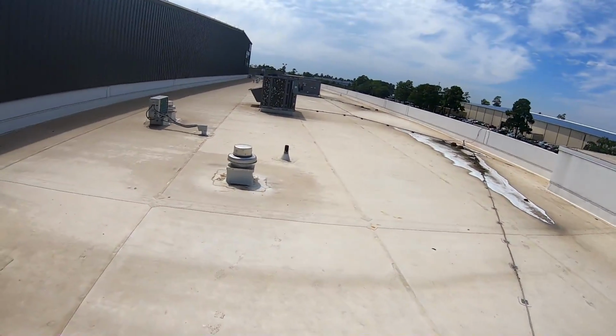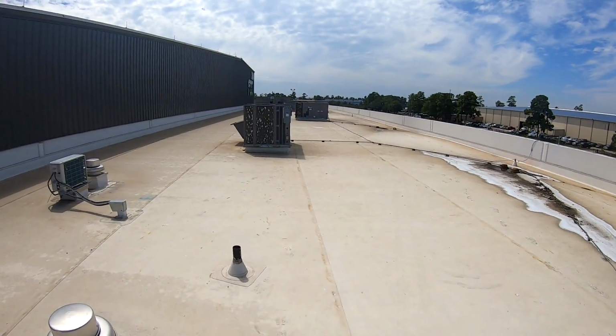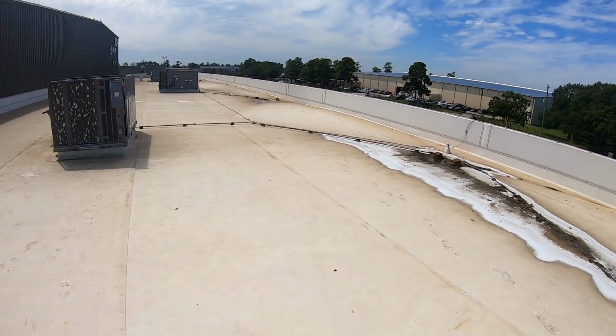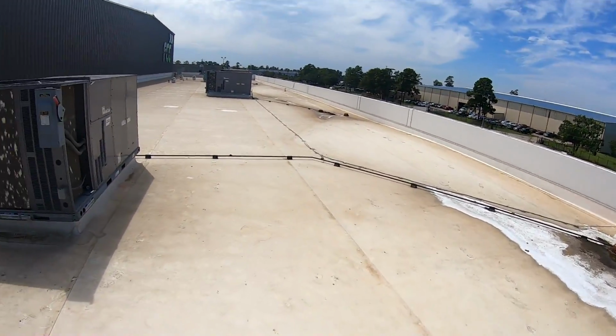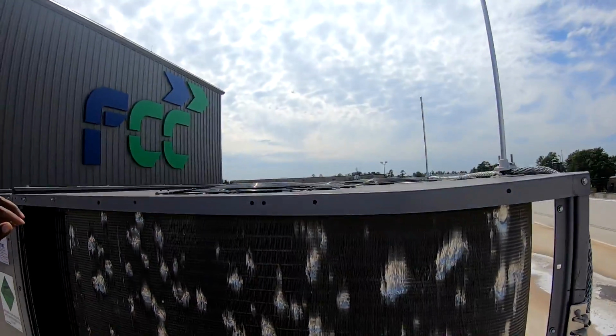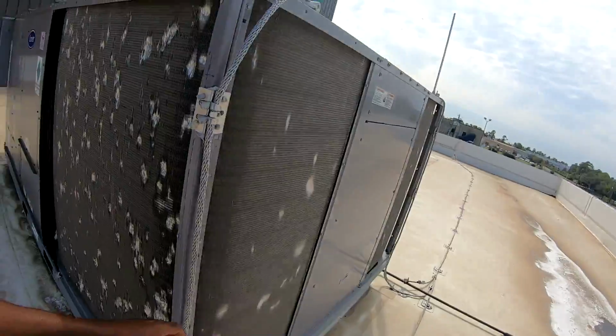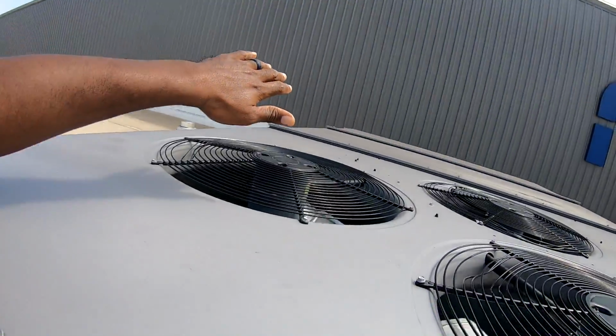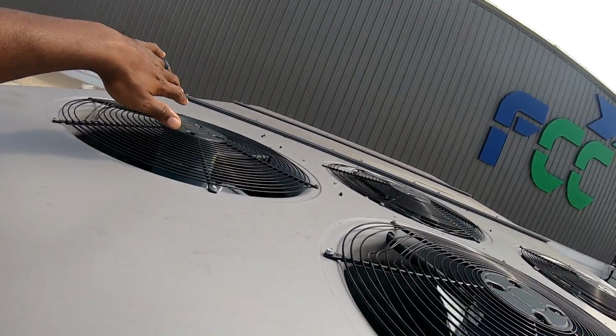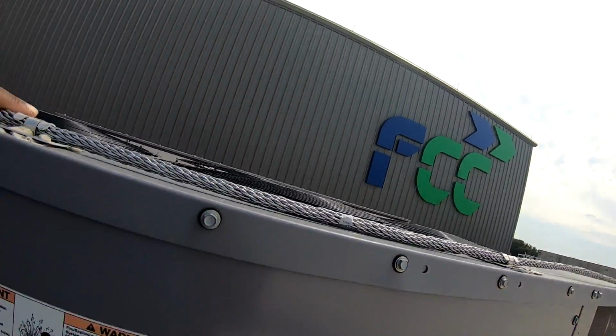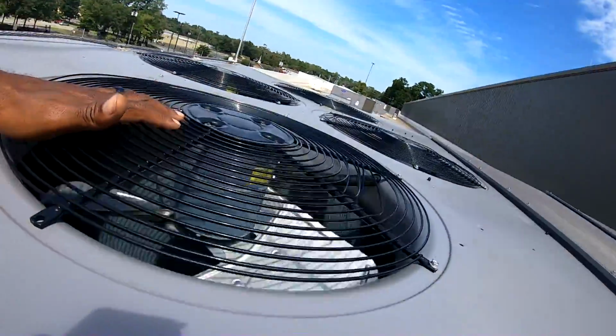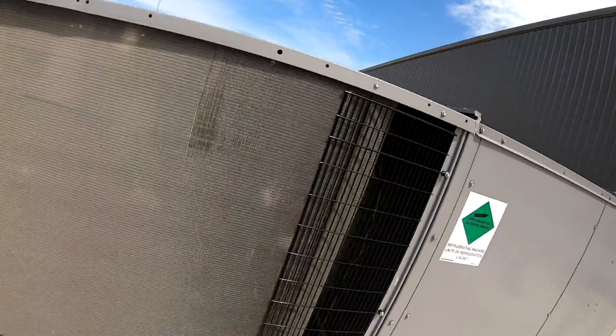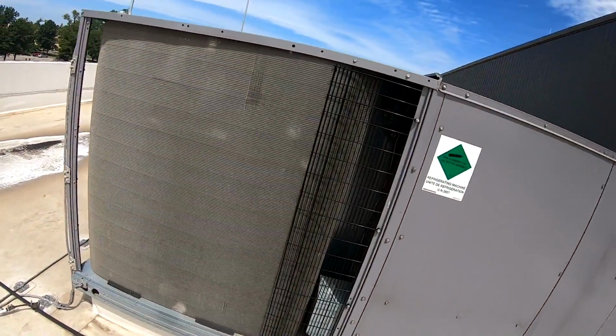All right, so anyway, I'm gonna go pop some ceiling tiles and see if I can follow some ductwork. Like I said, this is my first time on the roof, so now I can see how the units are positioned. When I was walking off the roof, I saw that this unit came back on. I don't know if they're ECM motors or not, but those fans don't seem to be running. So I bet this is the one right here. It's about 85 degrees up there, so they should be running, but they could be going off a pressure switch.